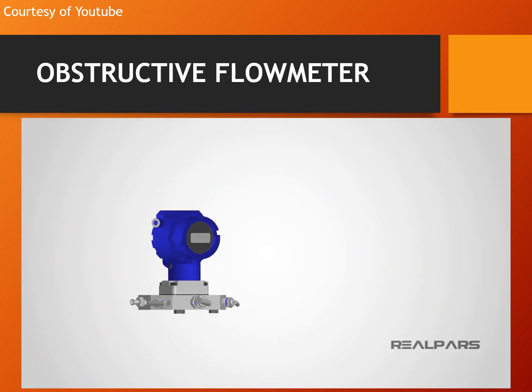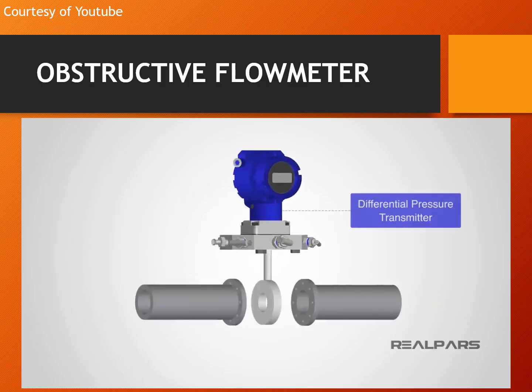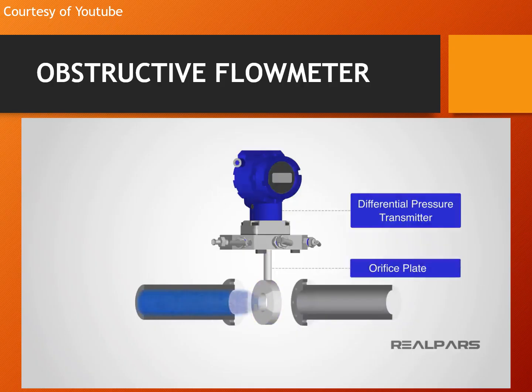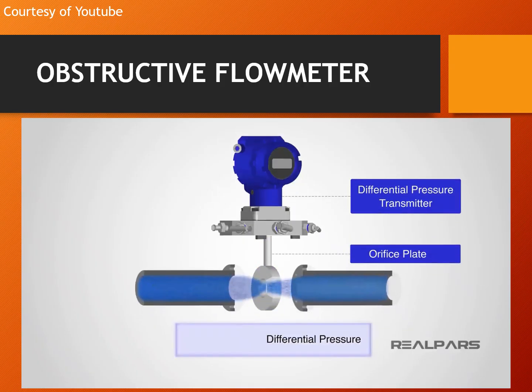A common method of flow measurement is done by using a differential pressure transmitter across an obstruction, such as an orifice plate. The differential pressure across an orifice is proportional to the square of the volumetric flow rate. Therefore, we need a square root extractor.